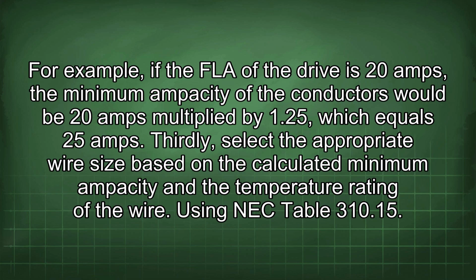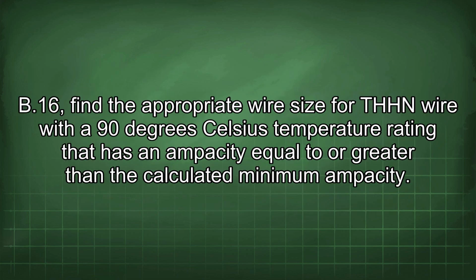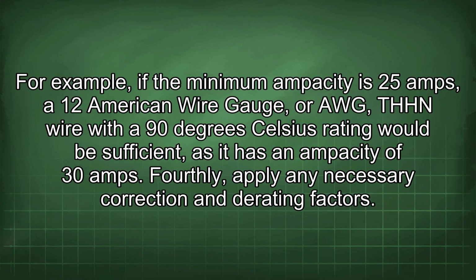Thirdly, select the appropriate wire size based on the calculated minimum ampacity and the temperature rating of the wire. Using NEC Table 310.15(B)(16), find the appropriate wire size for THHN wire with a 90 degrees Celsius temperature rating that has an ampacity equal to or greater than the calculated minimum ampacity. For example, if the minimum ampacity is 25 amps, a 12 American Wire Gauge, or AWG, THHN wire with a 90 degrees Celsius rating would be sufficient, as it has an ampacity of 30 amps.